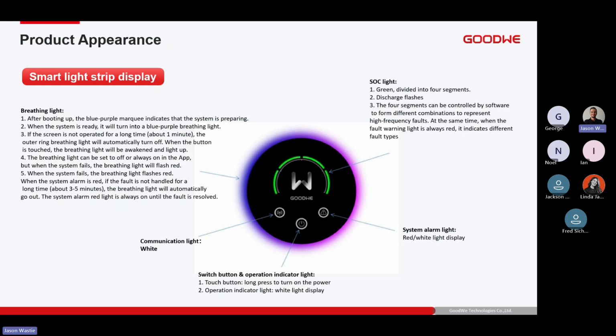This is some of the product appearance. So the LED light strip on the front of the battery allows us to see exactly what is happening on the battery, without having to go into any logs or anything. We can see exactly what the lights are doing. So this battery and all of our other batteries do have black start functionality. So we can black start and start the battery up, start the inverter up directly from the battery. We do not need AC or PV power in order to start up our inverters.